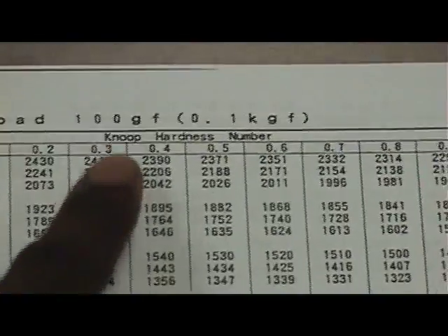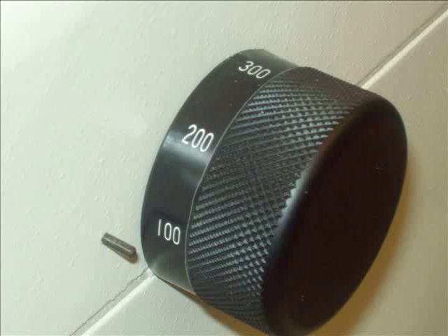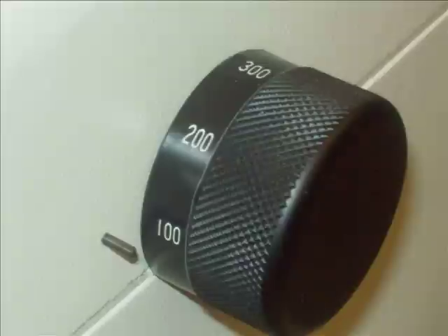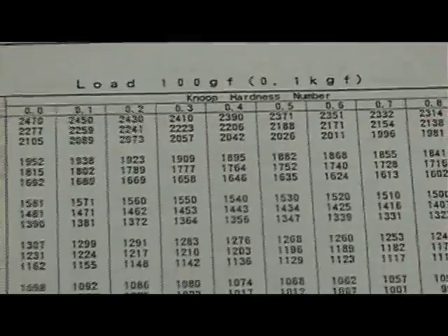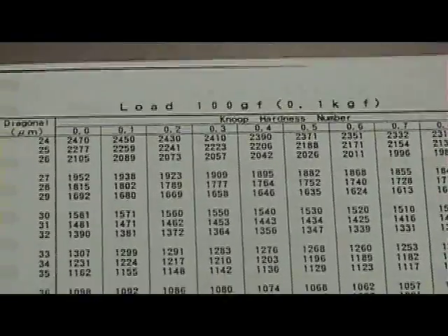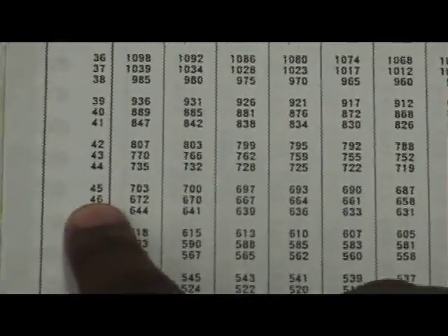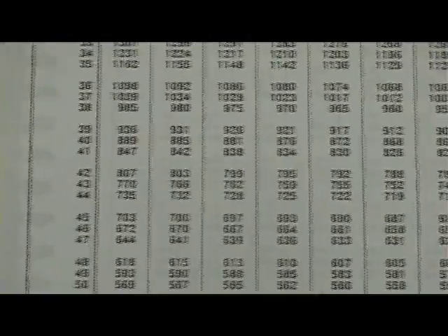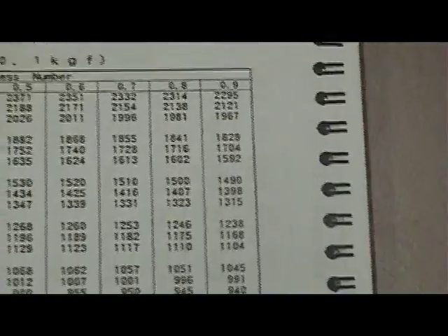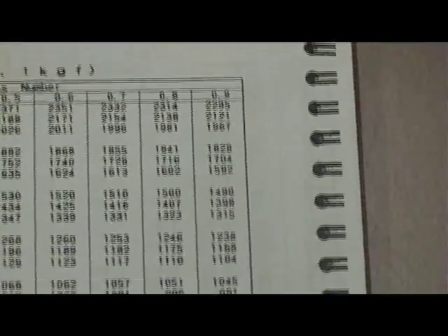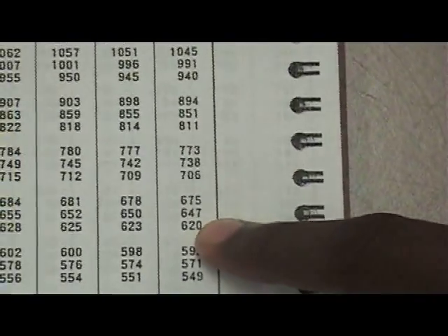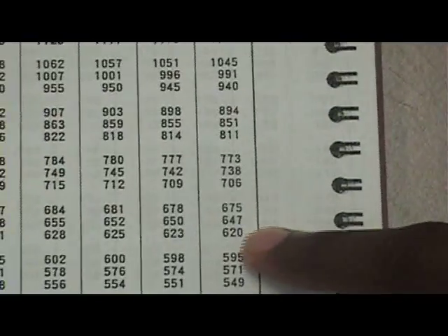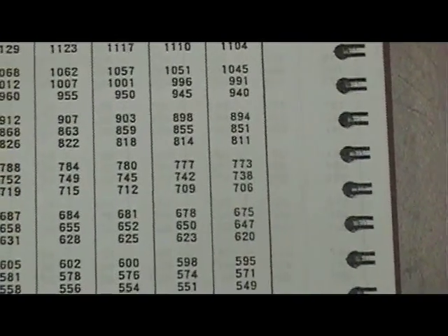Our load was 100 grams. Our diagonal measurement for the sample was 46.9. And the way we do it is we go all the way across the table for the 46. And then we go from the 0.9 all the way down until we're able to find 647. There's no units attached to it, so that is our number, 647.